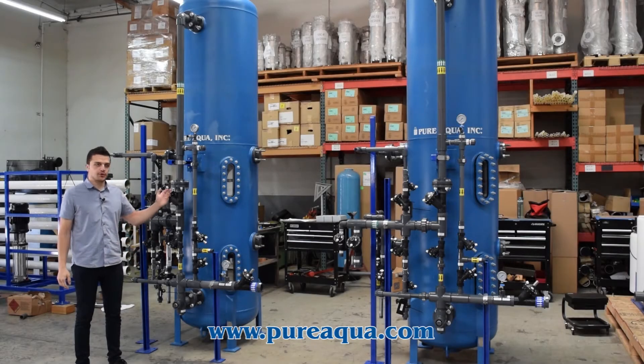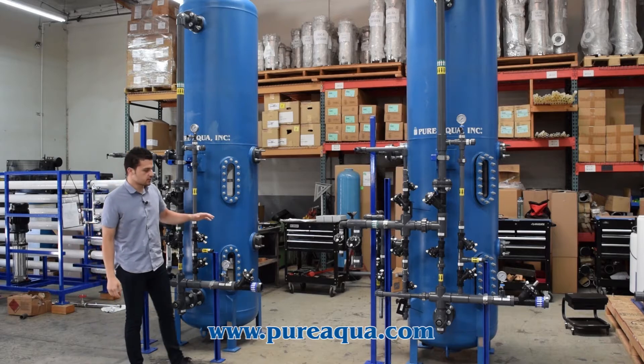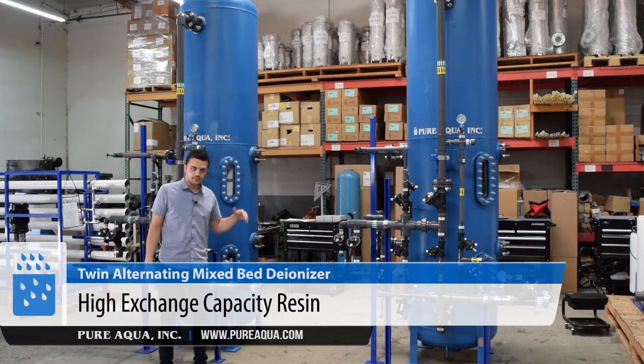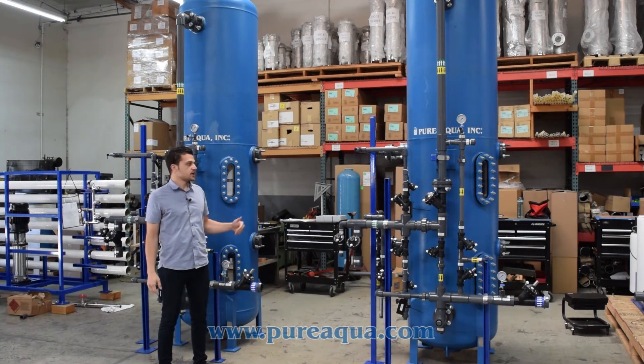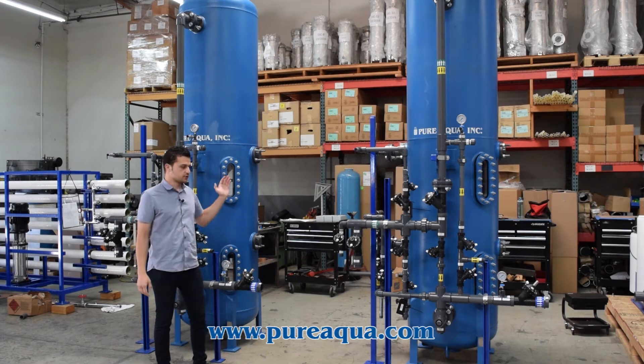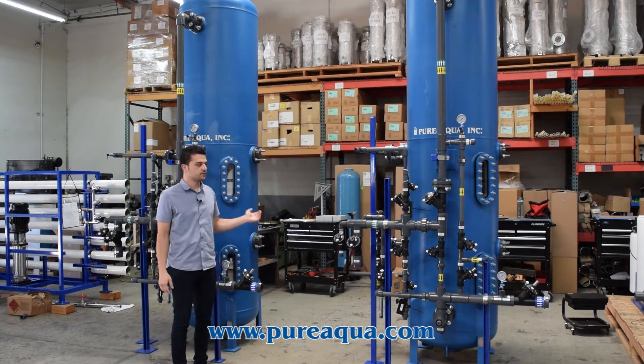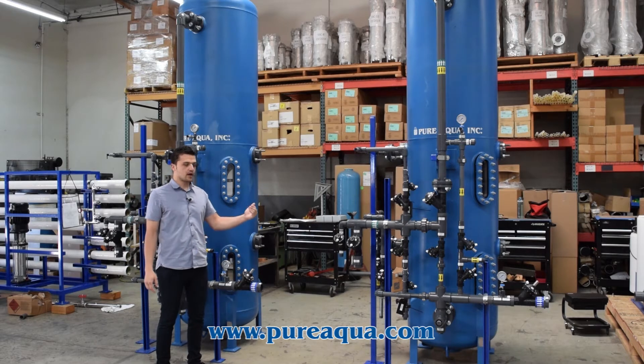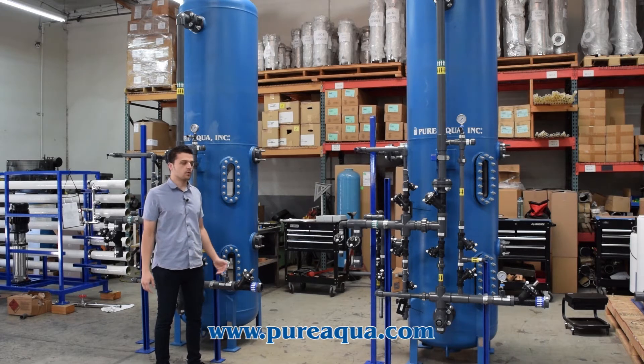We are utilizing Purolite high quality DI resin. Since this is a mixed bed, both resins are in one column and are regenerated independently. You have a cation resin and an anion resin. Typically you would feed about 3 ppm TDS into these DI units, and on the outlet side you would get about 18 mega-ohm water.